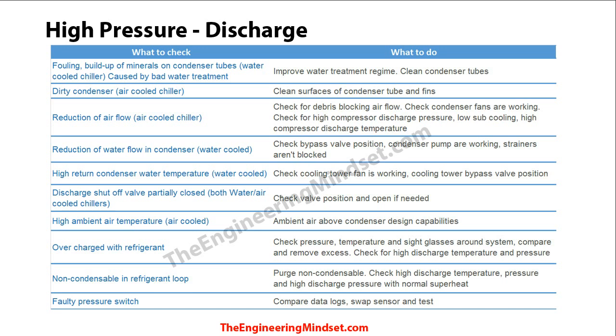Another common issue with air-cooled chillers is a reduction of airflow over the condenser, usually where debris has blocked the fins or fans so not enough air flows through to remove the unwanted heat. It could also be that one of the fans has stopped working or is behaving erratically, so physically and visually check that the condenser is clear of obstructions and all fans are working.